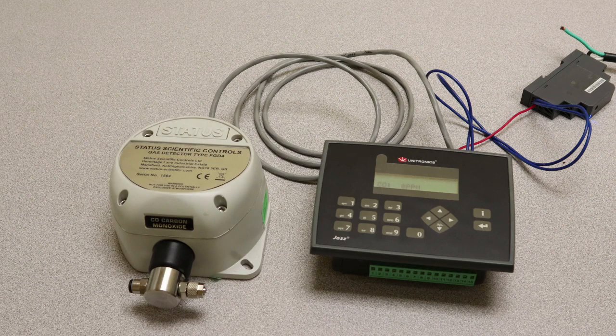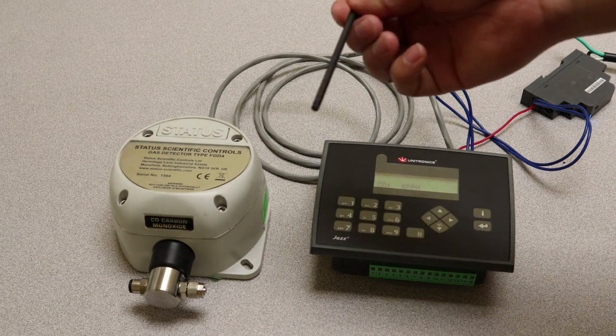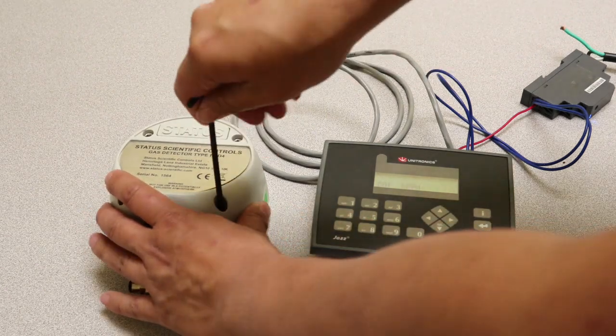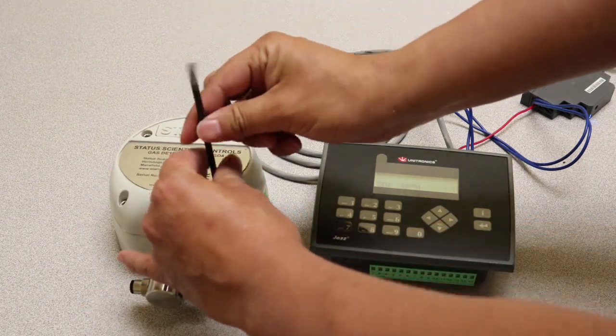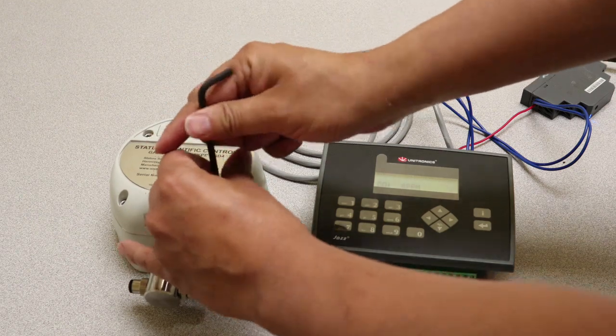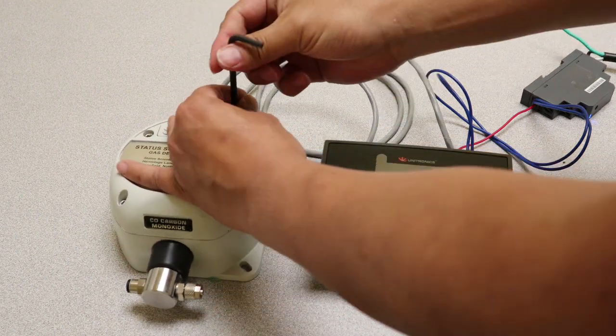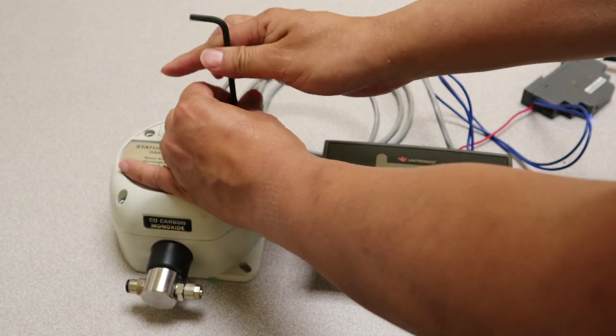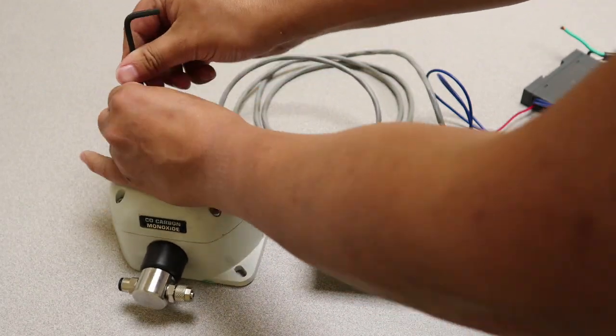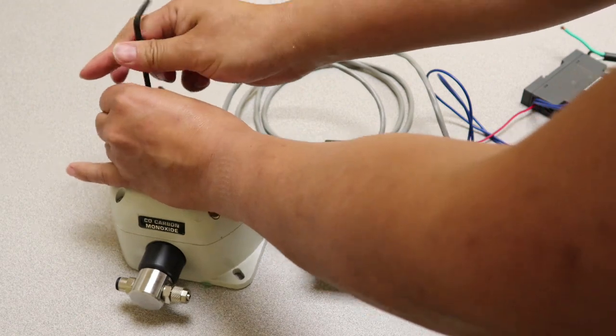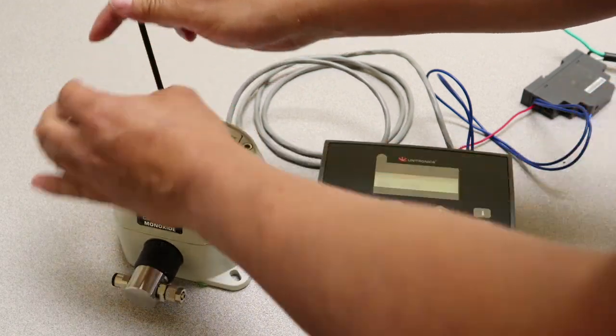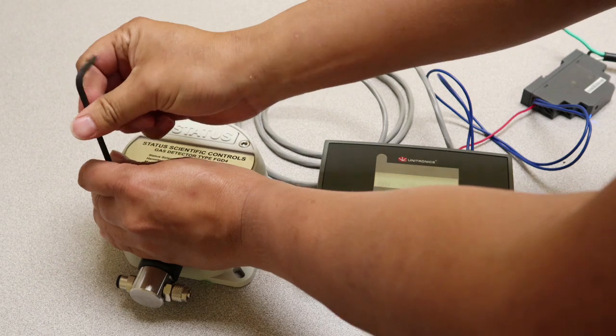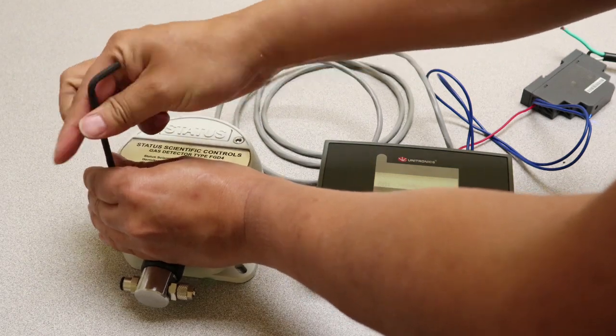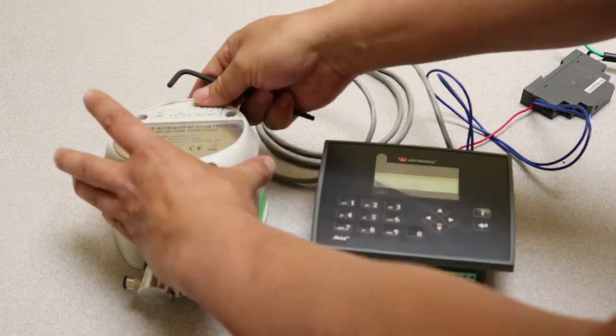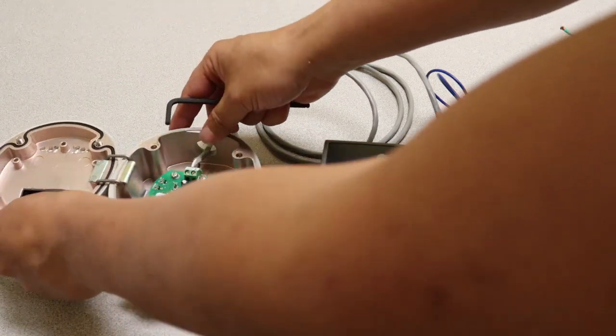To start with the calibration, first we need to open the transmitter unit. To open the transmitter unit, you will need an Allen key, and you're going to unscrew the 4 bolts here. The bolt will not come out. There's a locking mechanism in the case, so once you unscrew it all the way, it will just free spin at the top, so it won't fall off. Once you have it, you pop it open like this, and you can flip it open.